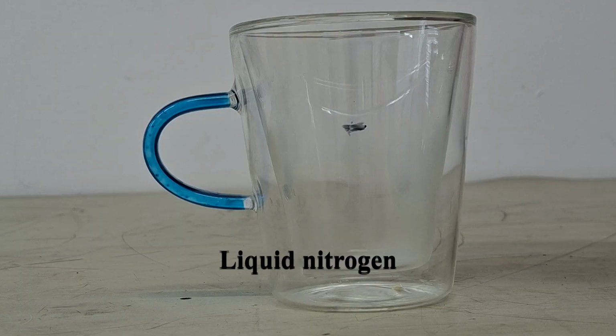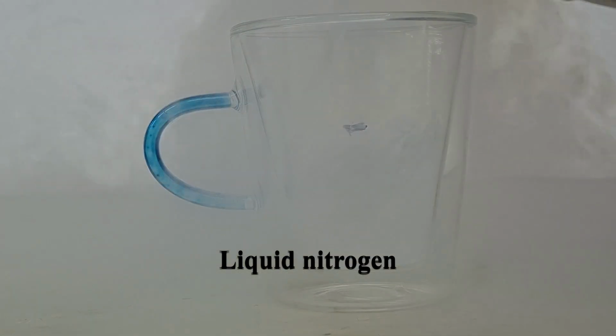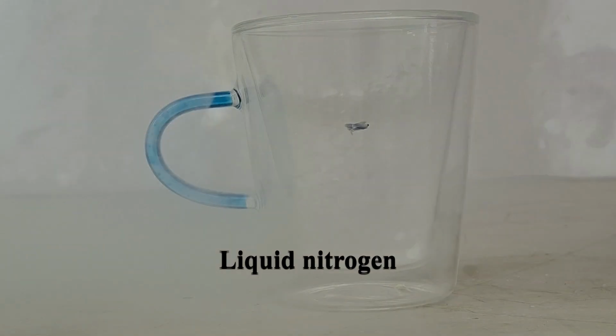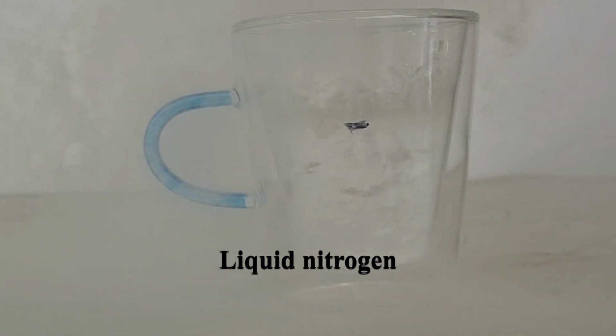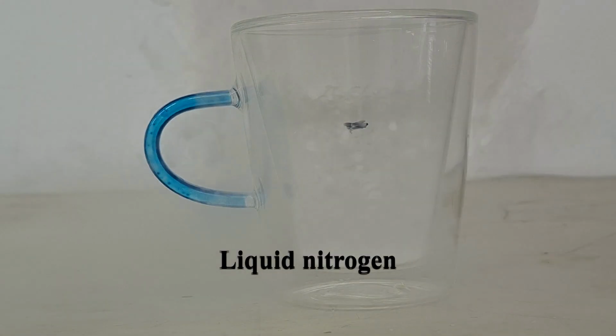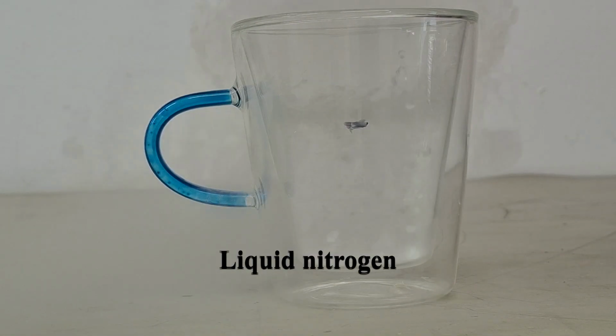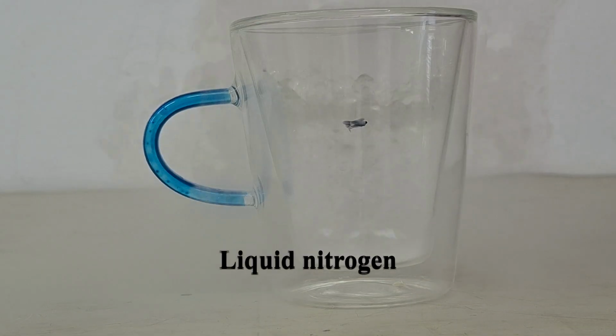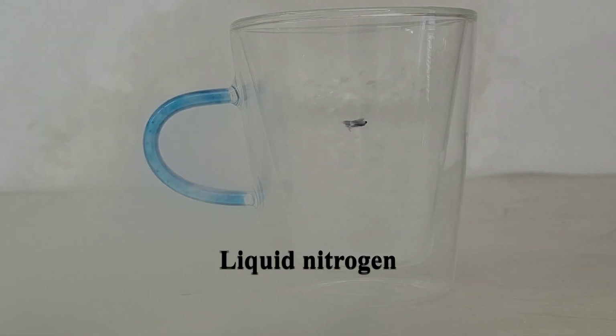We have seen the complex process of filling a helium dewar, so why does nitrogen not face this challenge? The key lies in density and vaporization behavior. The boiling point of liquid helium is 4.2 Kelvin, while that of liquid nitrogen is much higher at 77 Kelvin.